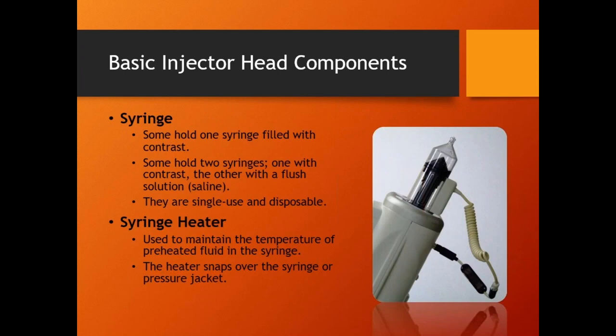Now, I talked a little bit about these before. The syringe and the syringe heater, which I just spoke about. Some of the contrast injectors just use one syringe. Angio injectors, for instance, just use one syringe. There's no point using a second syringe for saline in angiographic procedures. It's just the nature of the beast. It's how it's used. They don't use saline for radiographic or angiographic procedures. CT these days, almost all CT injectors do, not all of them, but nearly all of them. You can get pretty much any CT injector in a single syringe version. This one is called the Stellant D. D stands for dual, so the single version is called the Stellant S. It's just a contrast syringe, no saline. MRI injectors, on the other hand, all use two syringes, one for contrast, one for saline. All right.